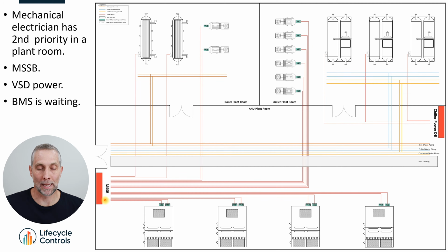They install the mechanical board and they start running all the mains power feeds out to all the equipment. So they install all the variable speed drives on the air handling units and on the pumps, and they start running the main power feeds. And they're hanging their electrical containment off of the pipe and duct. But again, the BMS contractor is waiting.